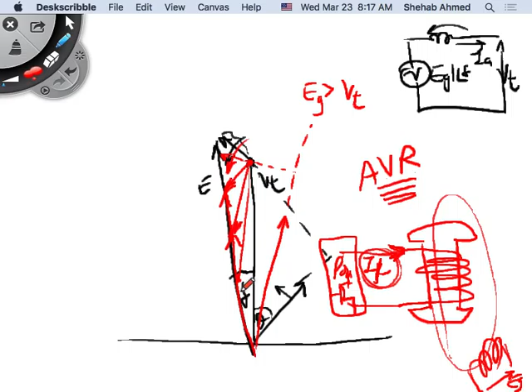In that case, you will be turning off the AVR. If you turn off the voltage control circuit of the generator, you have no control anymore. If you have a leading power factor load, it is causing the terminal voltage to be high, and you are trying to make sure you're not increasing that further or changing it by controlling E. That's adding capacitive load.